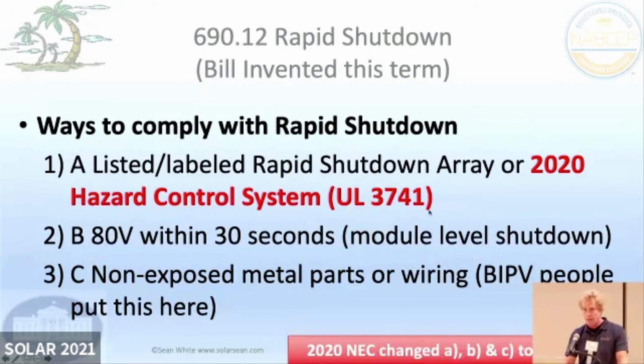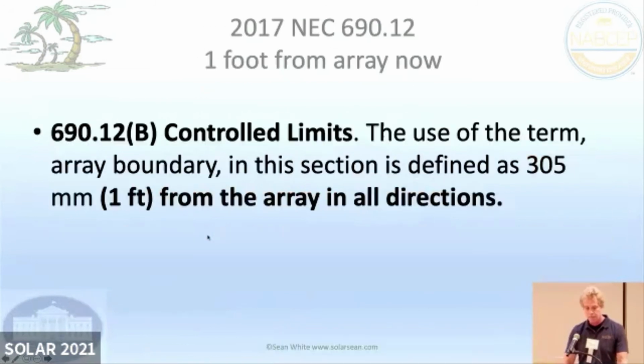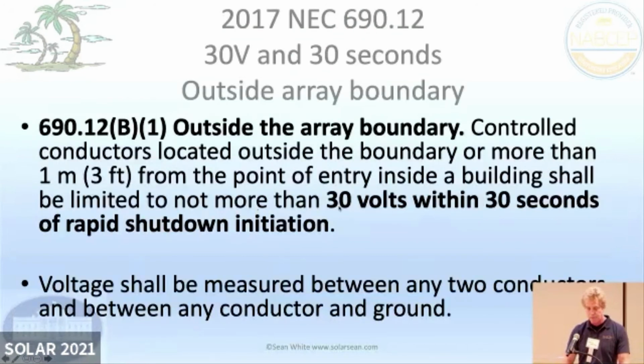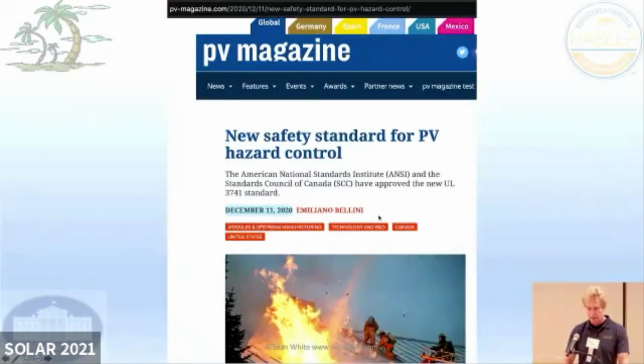And then that might make systems a little bit easier to maintain, because module level shutdown has a lot of pieces of equipment you might be replacing over the next 20 years. And when you're outside of the array, actually within 1 foot of the array, instead of 80 volts, you have to get down below 30 volts in 30 seconds. That's 30 volts in 30 seconds. That's rapid shutdown. This is the new standard that just came out, 3741, that we were looking for.